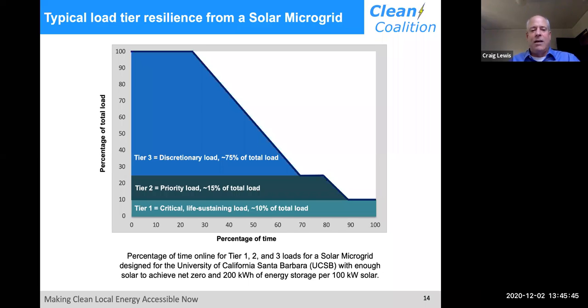In a typical facility, and the Santa Barbara Unified Schools are a great example, tier 1 loads are generally 10% or less of normal loads. Tier 2 loads are about 15%, and the other 75% are discretionary. A solar microgrid can guarantee your tier 1 critical loads stay on forever. Tier 2 loads can be maintained about 80% of the time, and even tier 3 loads can be kept on at least 25% of the time, so everything can be on for a good percentage of the time, and critical loads never go off.